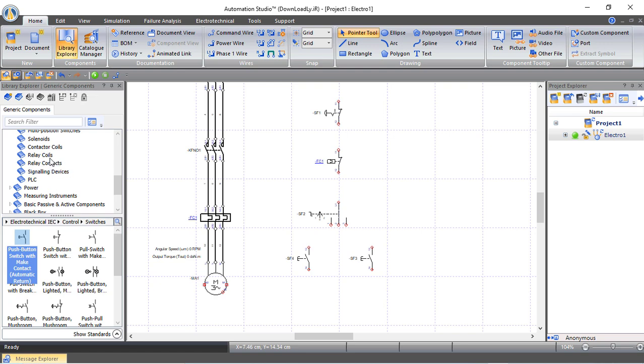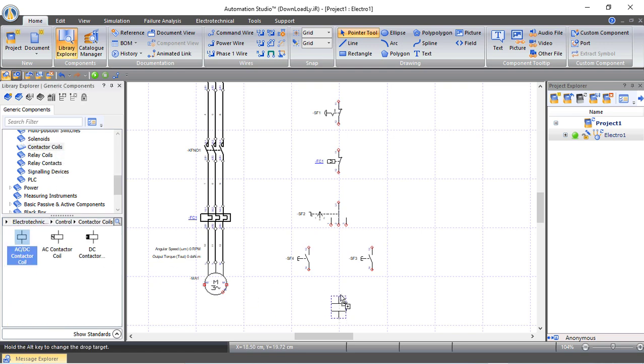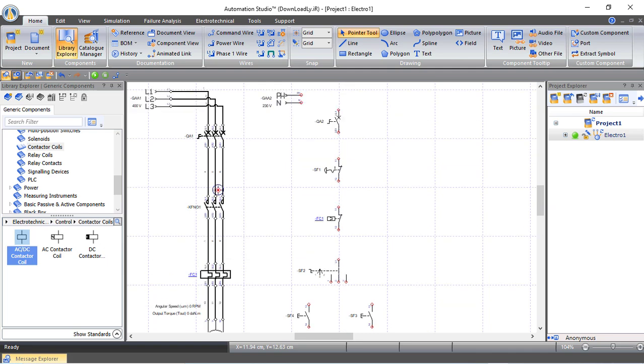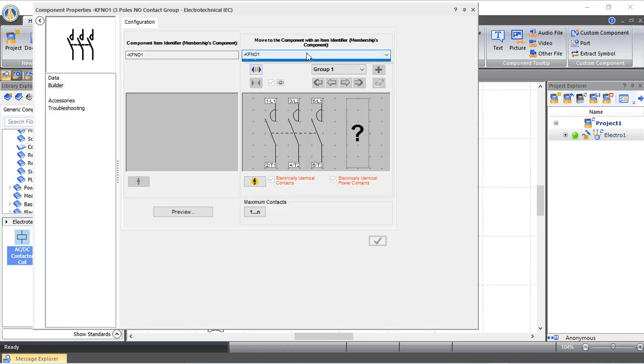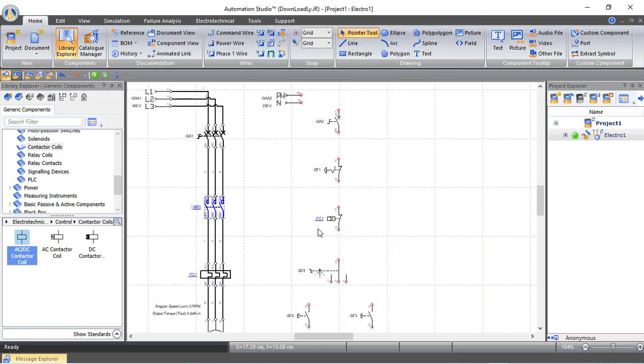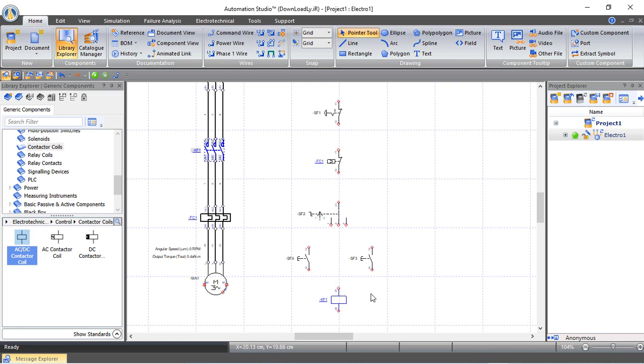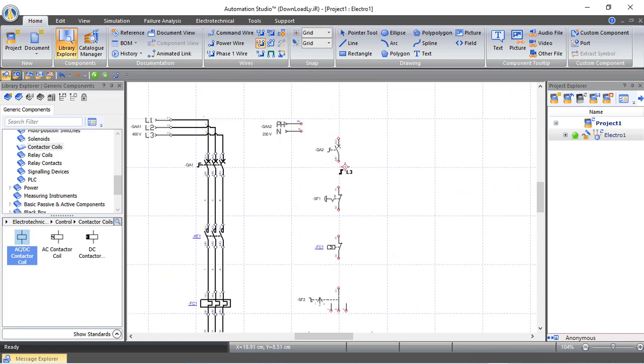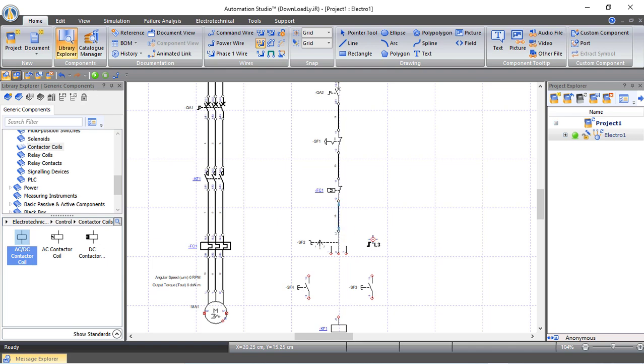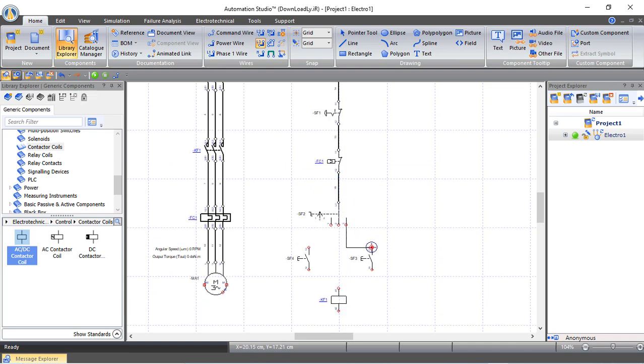Now we bring the contactor coil. We name this contactor KF1, linking it to the corresponding coil. The circuit connects from the circuit breaker through the stop push button, through the thermal overload contact, then to the start push button, and then to the KF1 coil. The second push button also connects into this path leading to the contactor coil.